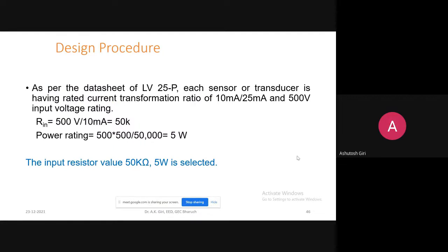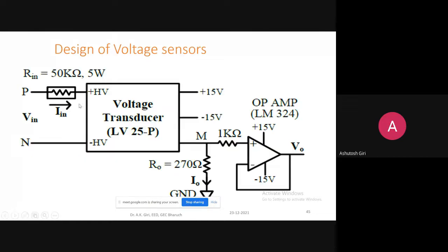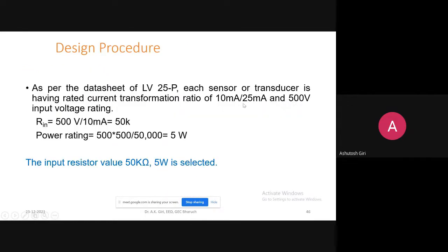How to design it? As per the data sheet of the low voltage LV 25P—LV 25P is the model. Each sensor or transducer has a rated current transformation ratio of 10 milliamps to 25 milliamps and a 500 volt input voltage rating. That means we cannot keep more than 500 volts here, and the input and output current—from this terminal and this terminal—is given in the data sheet as a 10 to 25 milliampere current transformation ratio.